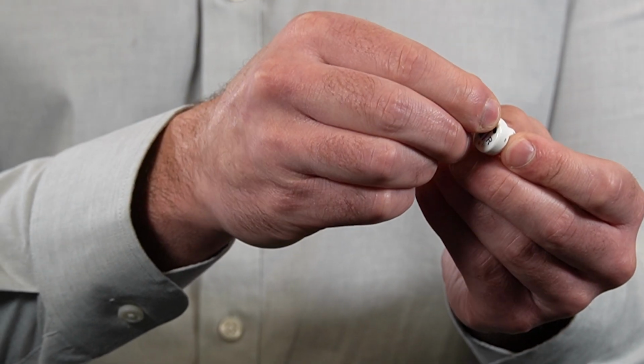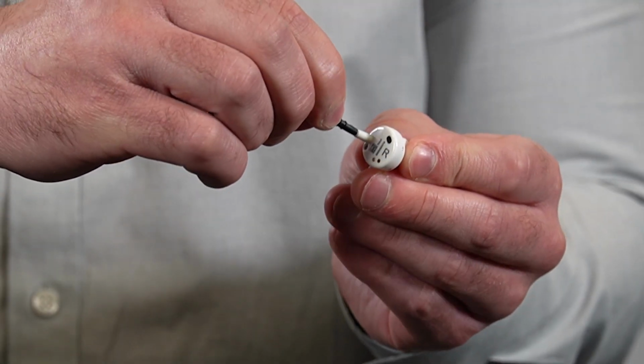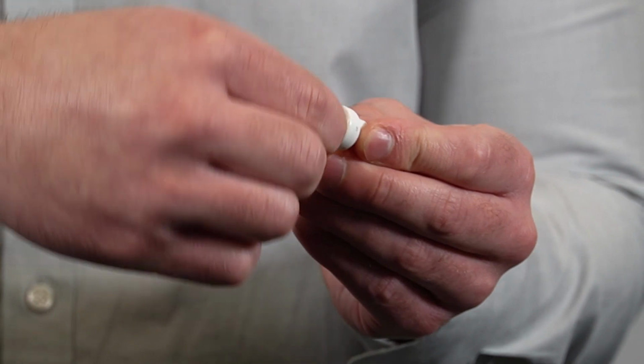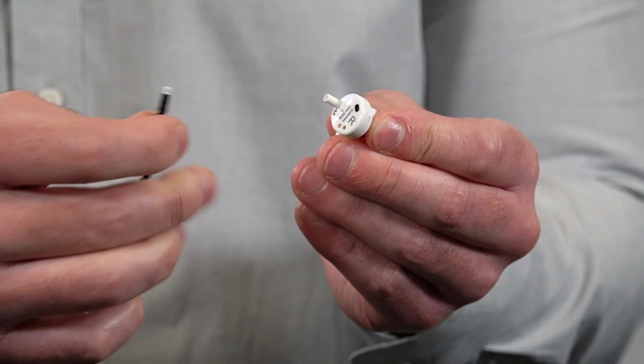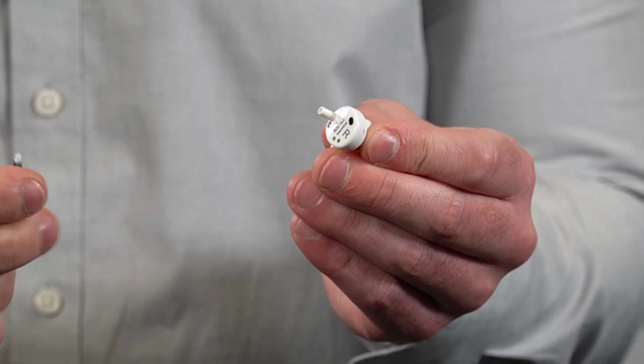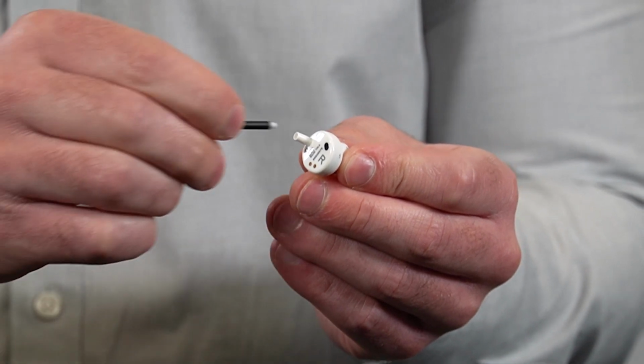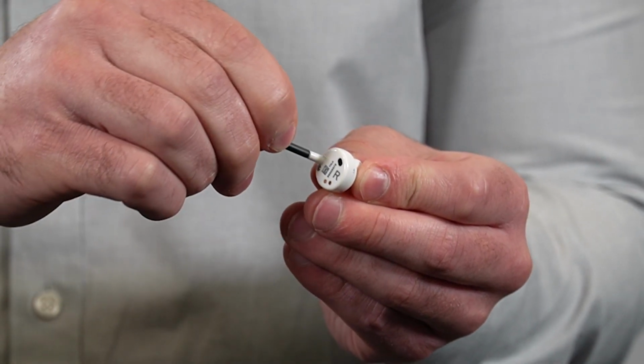First, remove the ear tip from your device. Next, using the wax stop tool, insert the star-shaped removal end into the used wax stop. Pull the tool up to remove it. Turn the tool over to place the new wax guard on the tip and press firmly into place.